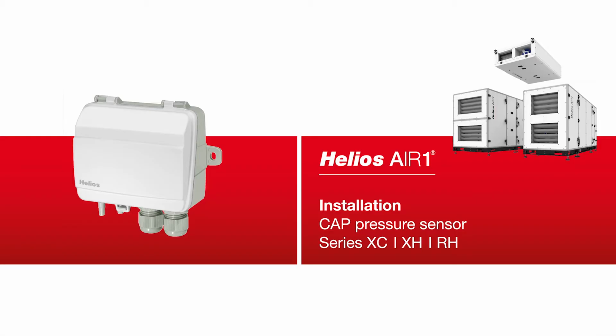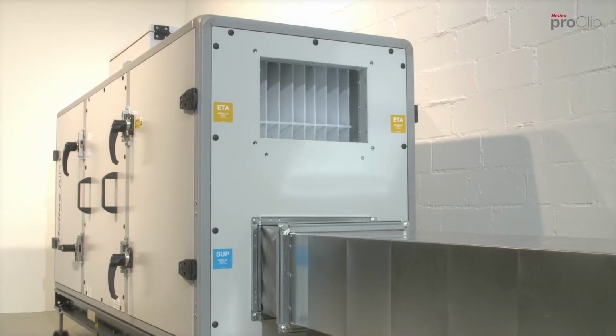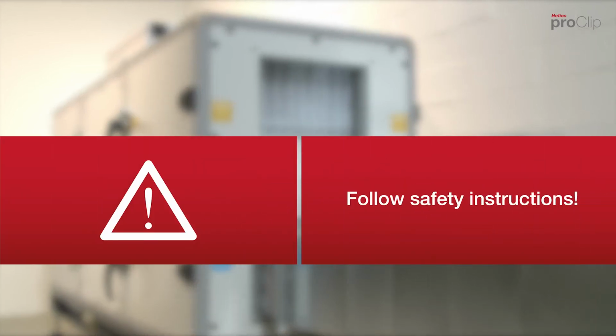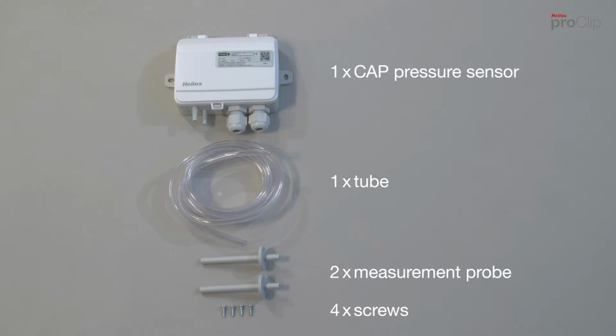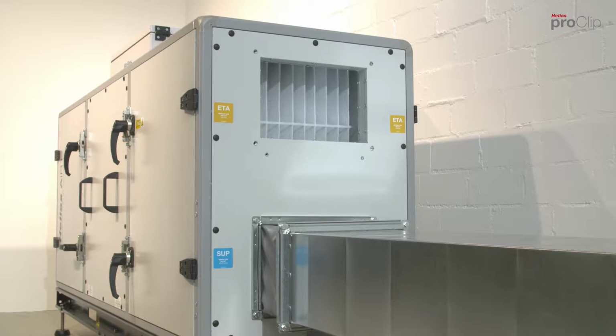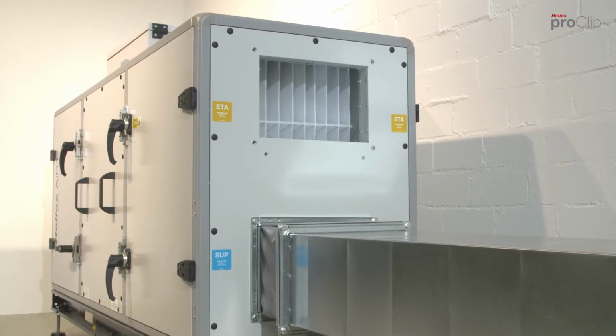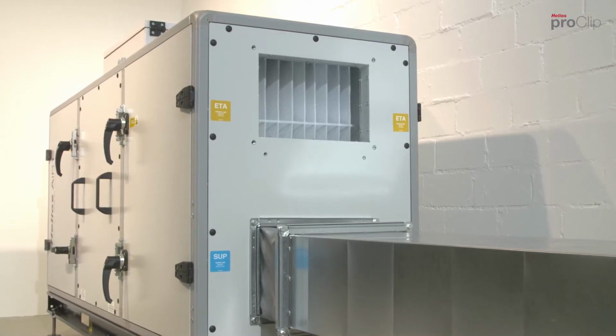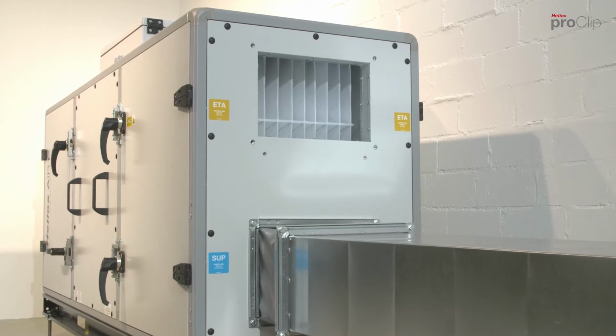In this proClip for Helios AIR1, we will show you how to install the CAP pressure sensor. Please note the safety instructions in the relevant installation and operating instructions manual. Before starting installation work, check the scope of delivery for completeness. The CAP pressure sensor is required for controlling the AIR1 units in the constant pressure ventilation mode.